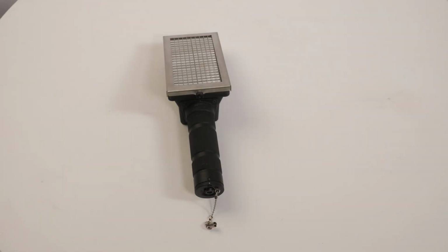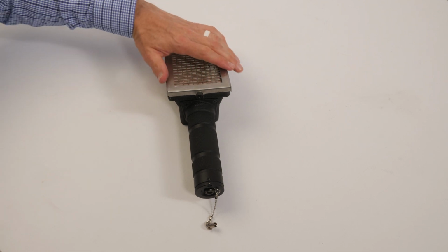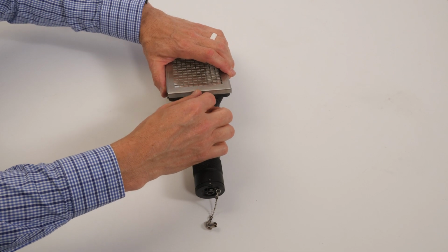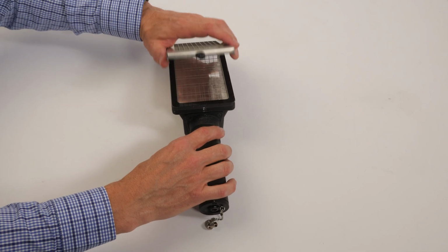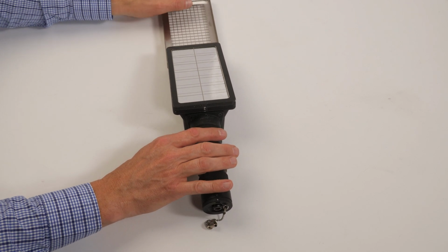To replace the Mylar window and protective screen, face the probe up, loosen the captive screw, and open the hinged protective grate. The Mylar window is prefabricated into a one-piece part and should be easily removed and replaced as one piece. It blocks ambient light from reaching the scintillator. When damaged with even a small pinhole, light leaks occur and cause inaccurate readings by the scintillator.